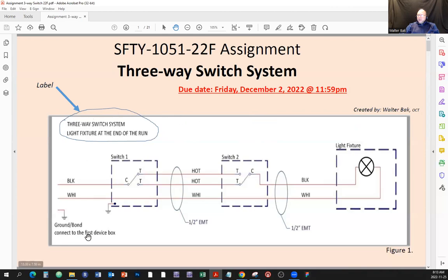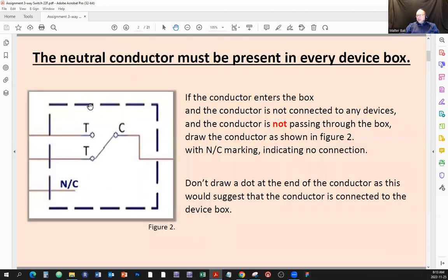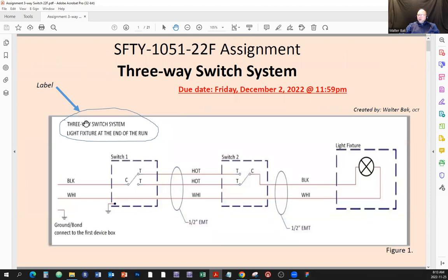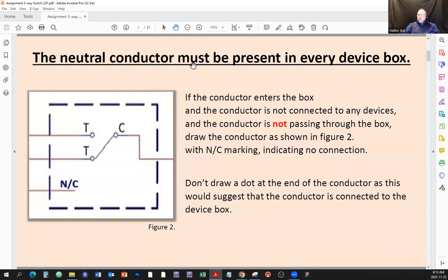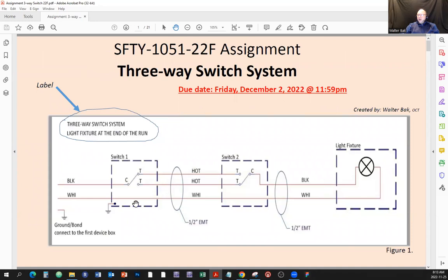Let's talk about some rules. The neutral — the white neutral conductor — must be present in every device box. In this case, no problem because the neutral goes through all the boxes and ends up at the load. Do we have a neutral present in each box? Yes, yes, and yes. There will be scenarios when the light fixture is in the middle or at the beginning of the run where not all boxes will have the neutral provided naturally.